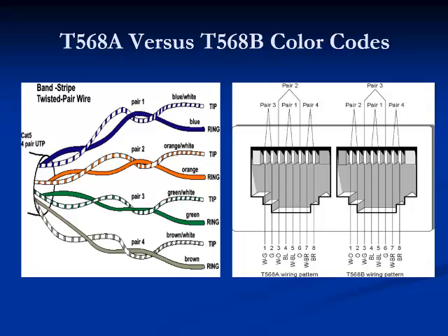Either of the two is the correct choice as long as the same connection is always used throughout the cabling system. T568B is much more common in commercial installations, but T568A is now recommended for new configurations. T568A is the required configuration for residential installations in accordance with 570A.